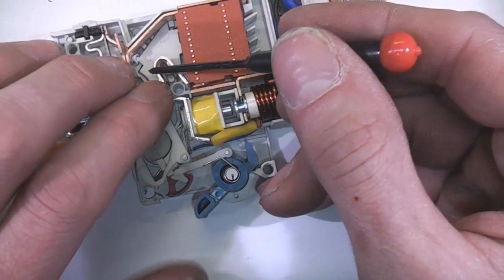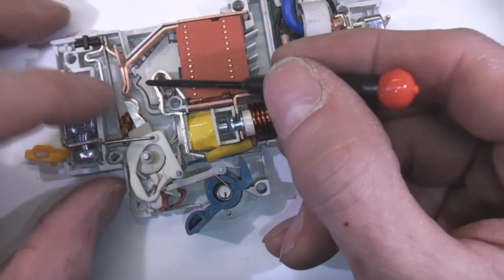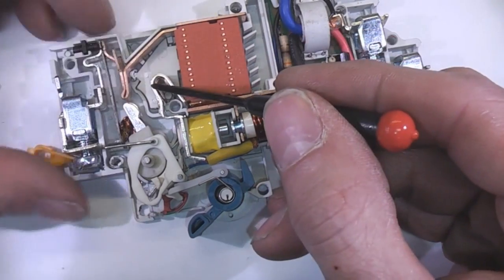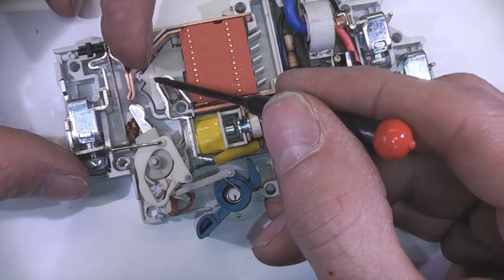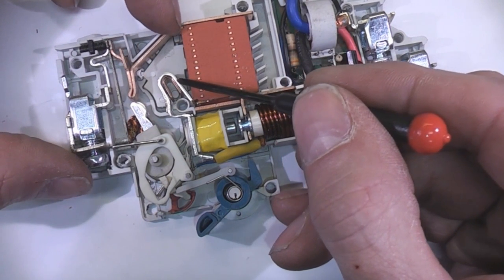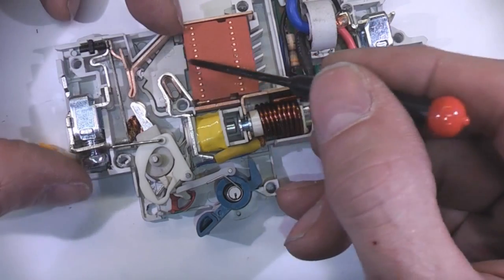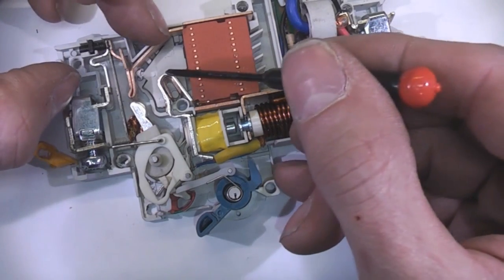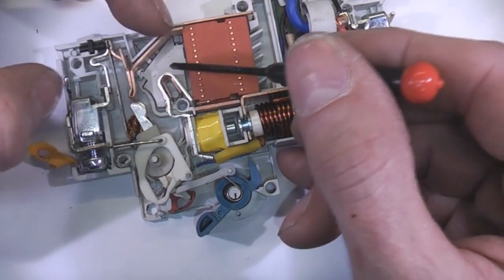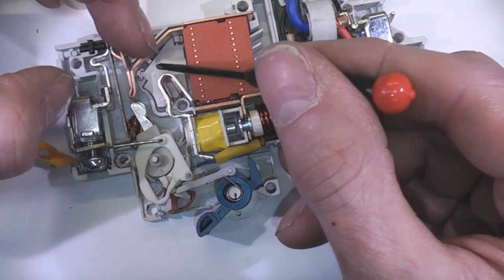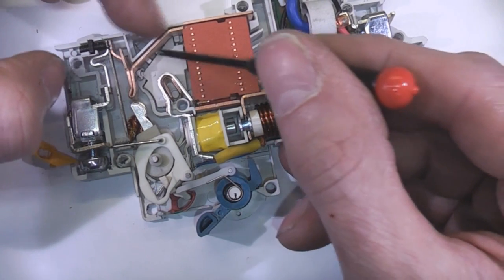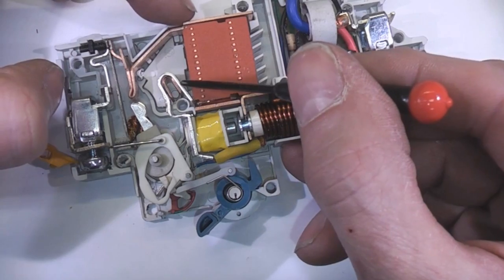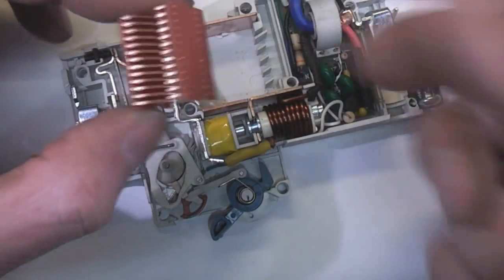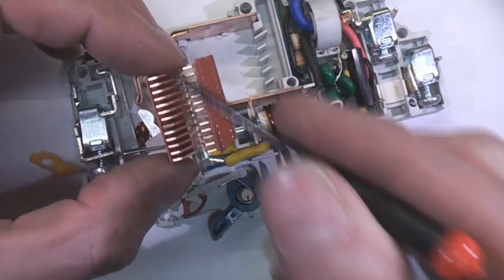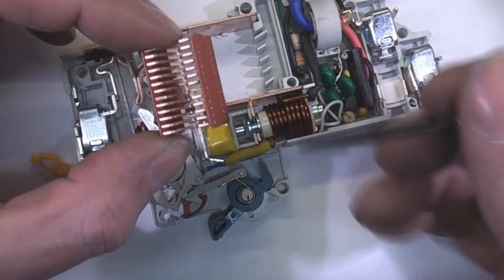But say if we carry on and assume it's still arcing, that arc will potentially travel down here. And arcs tend to like to open up. Obviously you've all seen Jacob's ladders where you get the spark, the arc increasing as it goes, they just tend to like opening up. So the arc will travel up here and then into this part here. Now what this is, is just a stack of plates. These are copper plated, but they're actually steel plates.